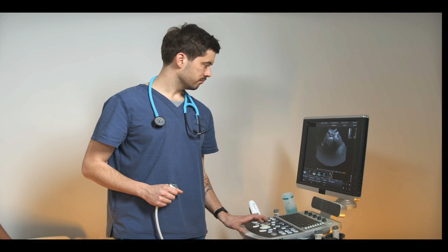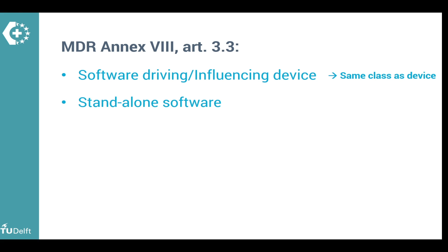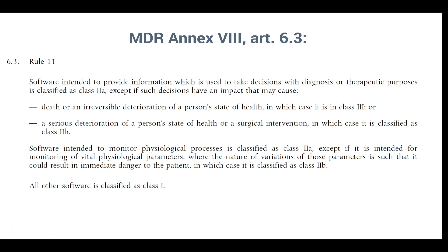Article 3.3 of Annex 8 distinguishes two types of software. There's software driving or influencing a device, in which case it will get the same class as the device, and software that is independent of another device, apart from the computer it runs on, of course, which must be classified according to its own use and properties. Well, that's stated in Annex 8 Rule 11, which is in Article 6.3, since software is considered an active device.